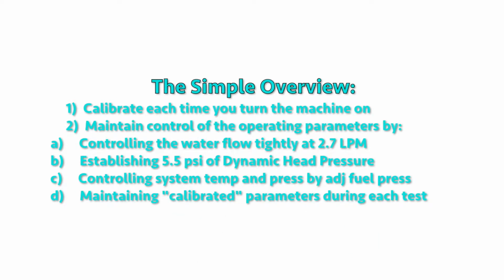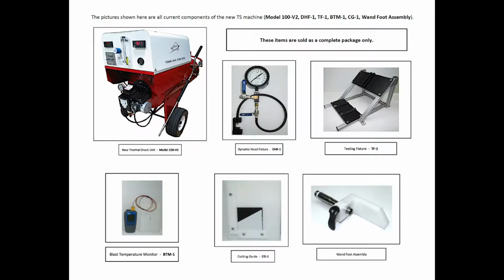A simple overview of testing with the thermal shock machine is, first of all, you calibrate each time you turn the machine on. Secondly, you maintain the operating parameters that produced your required dynamic head pressure by doing the following. Tightly control the water flow rate at 2.7 liters per minute. Establish 5.5 psi of dynamic head pressure by adding the proper heat to the water. Control the system pressure and temperature by adjusting the fuel pressure. And finally, maintain calibration operating parameters during each and every test.